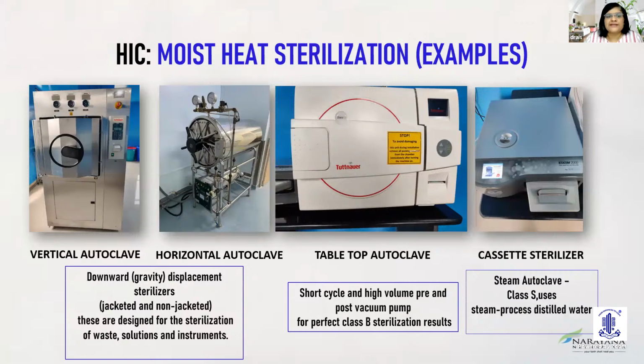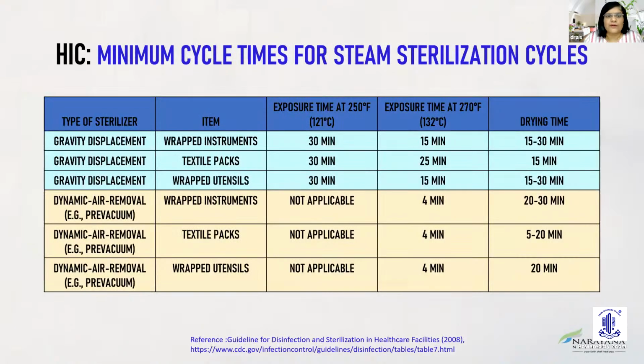Moist heat sterilization examples that we are using are the autoclaves. These are the gravity displacement sterilizers, which are jacketed and non-jacketed, designed for sterilization of waste solutions and instruments, a horizontal autoclave, a tabletop autoclave, and a cassette sterilizer. The tabletop autoclave that we are using has a short cycle and high volume pre and post vacuum pump for perfect Class B sterilization results. And the steam autoclave, which is a cassette sterilizer, utilizes a steam process with distilled water.